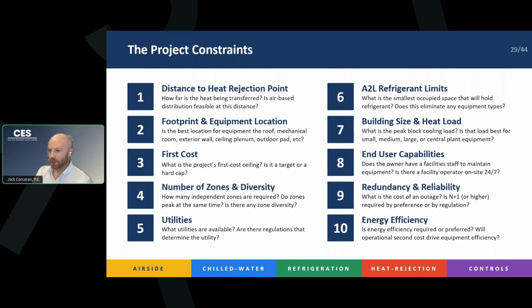Instead of ductwork, right? This first and second questions and points that we're asking ourselves are kind of combined, right? And so in VRF systems, you're sending small refrigerant to a lot of zones. You're not sending ductwork. You don't have huge mechanical rooms. You don't have big plants. For the most part, your indoor units and your outdoor units are small. Your refrigerant piping is small. So if your architect is telling you you don't have a lot of space, maybe think about VRF as a solution.